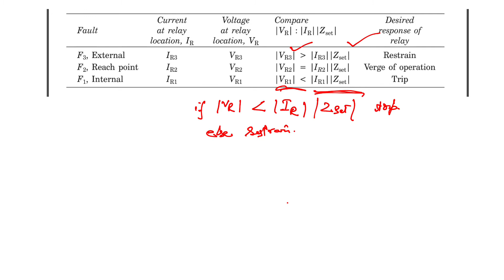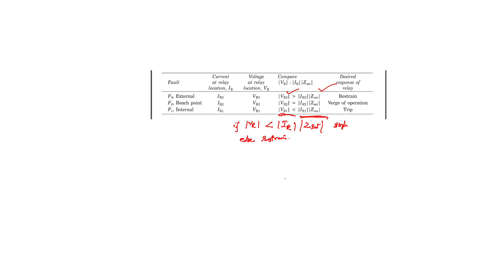So this is actually the trip law. That is, if VR is less than IR into Z set, it will trip, otherwise it will restrain. And writing this in other form, we get the magnitude of VR divided by IR is less than Z set, then it will trip, else it will restrain. Now the ratio is the ratio VR and IR.